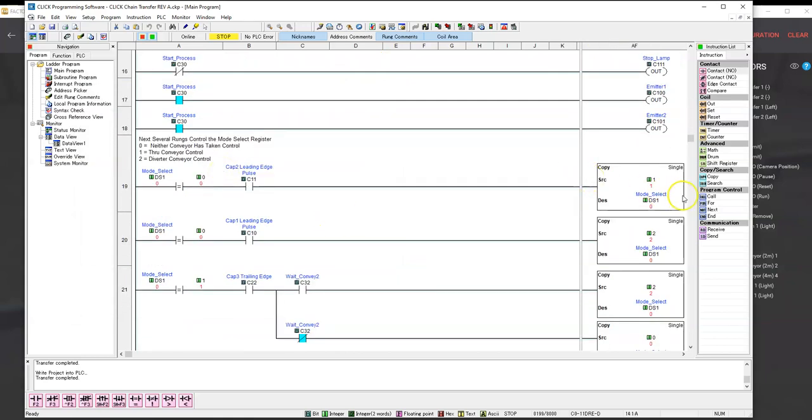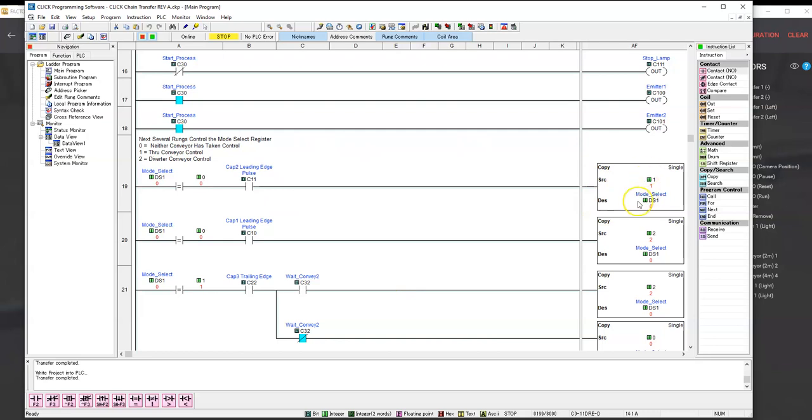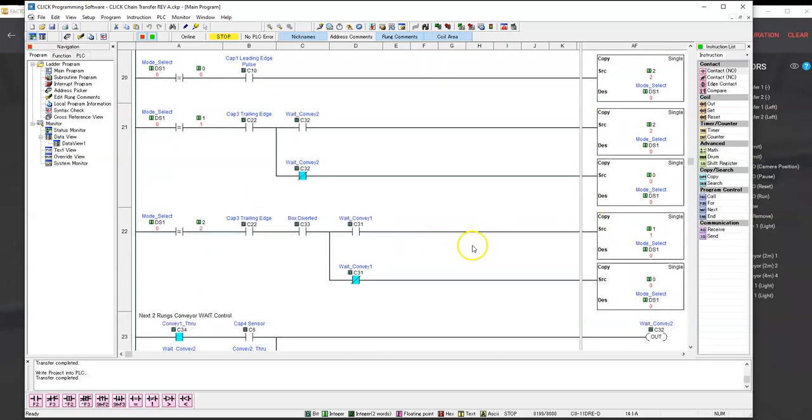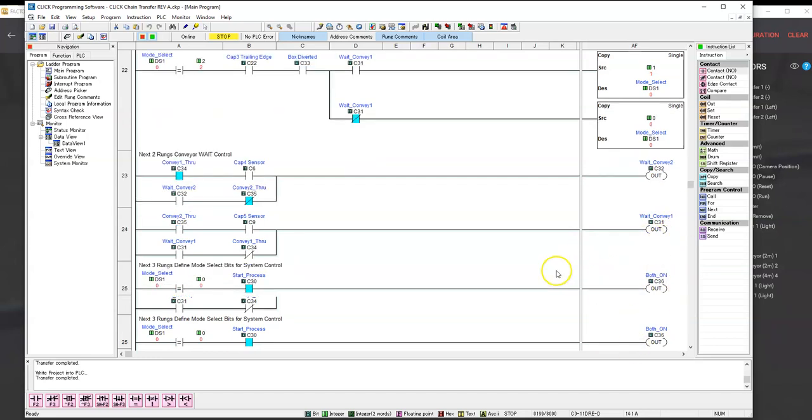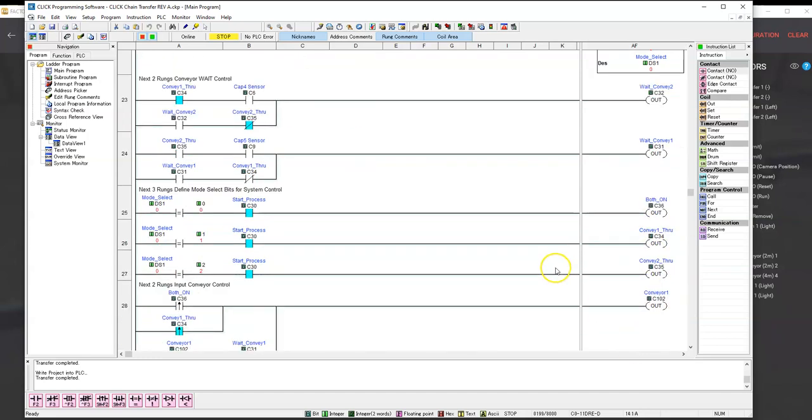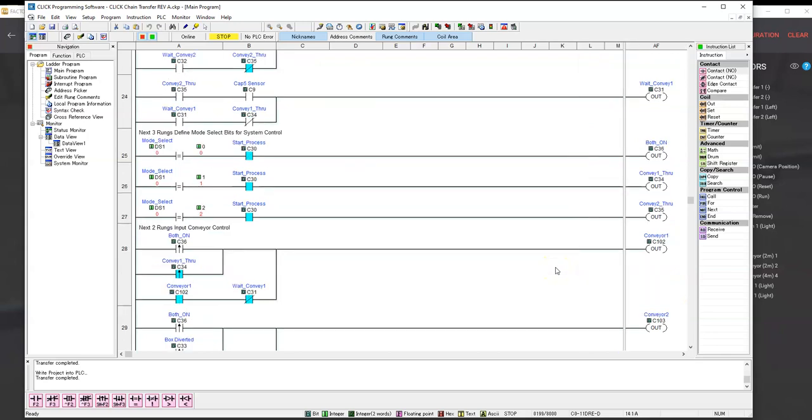If we look at the programming a little bit further, besides the edge triggers, what we use here is we have an integer register that tells us what type of mode we're in. When we start out, neither conveyor is in charge, so it's mode 0. If conveyor 1 or path 1 is in charge, then it's mode 1. And path 2 is in control, then it's mode select is 2. So we have logic that just moves that mode select in there.